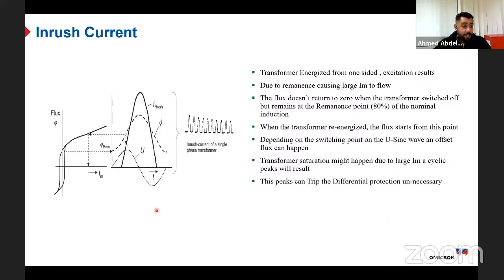Due to the effect of hysteresis, once I switch the transformer off, this flux will never go back to the same residual flux, because it is a buildup. So if after a certain number of days or a month the transformer is energized and I then switch it off, the flux will be reduced, but it will never go back to zero. It will go back slightly more than the remnant. Later on, I decide to energize my transformer, and depending on at which instant in the voltage sinusoidal wave I energize it, this remnant will increase, and sometimes a very high magnetizing current will flow inside the transformer. This is called the inrush.